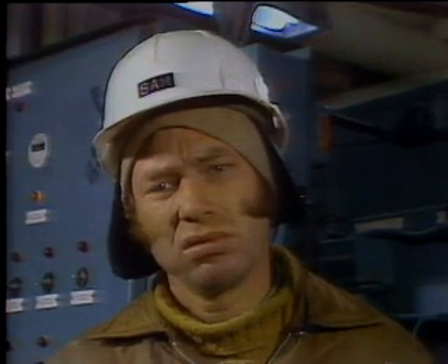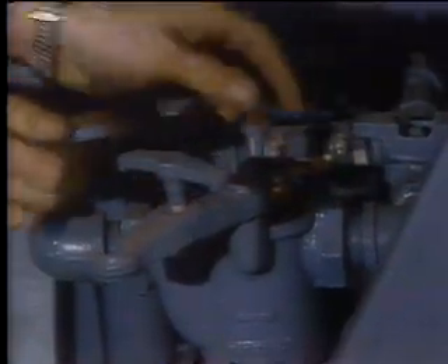The evaporator temperature dropped and reduced the pressure. Well, what caused that to happen? And how do I prevent it in the future? Well, it's usually caused by trying to introduce too much cool water into the unit too quickly. But if you've been watching it closely and you're still having a problem, then I'd say your incoming water isn't being preheated properly by the heat exchanger. And that can be traced back to the blowdown strainer basket.